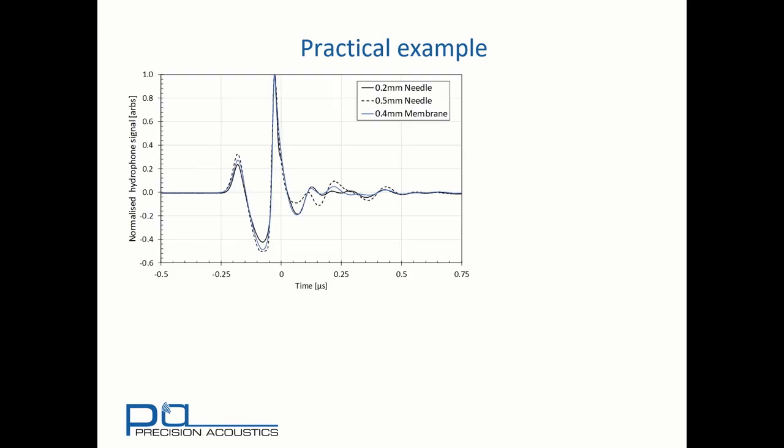Let's have a practical example of hydrophone deconvolution. Here we have a diagnostic ultrasound waveform that has been measured with three different hydrophones. For ease of visualization, they have been normalized to their peak positive excursion.